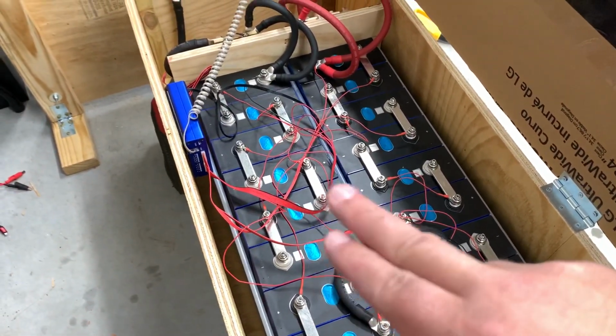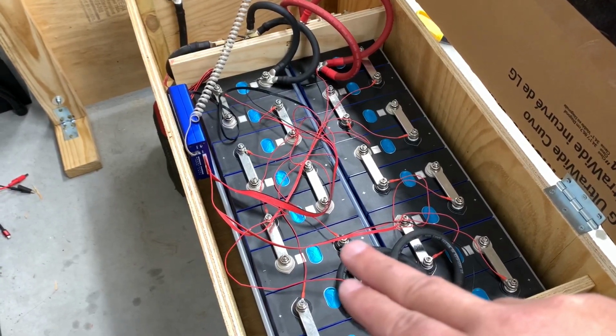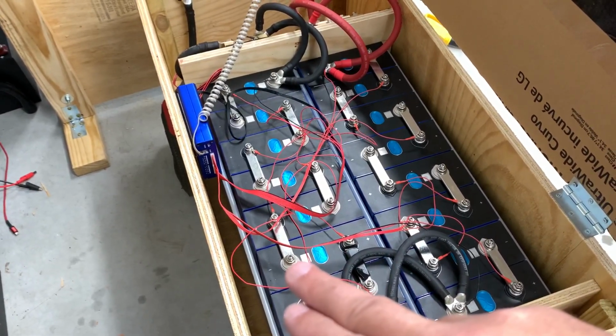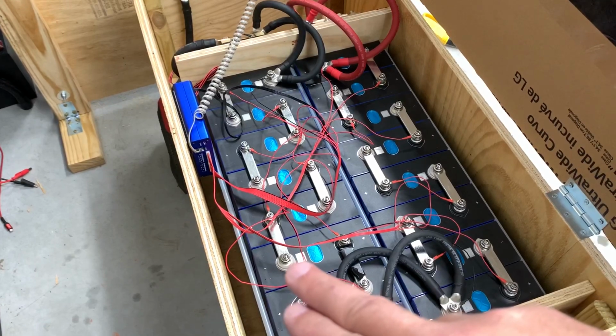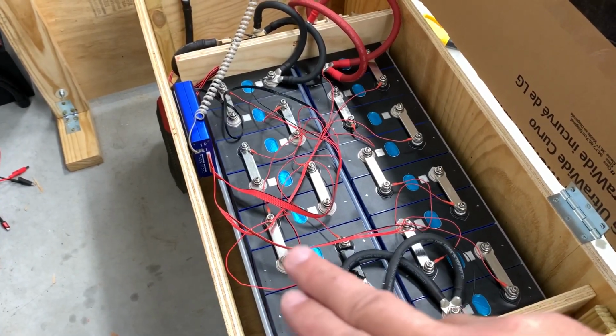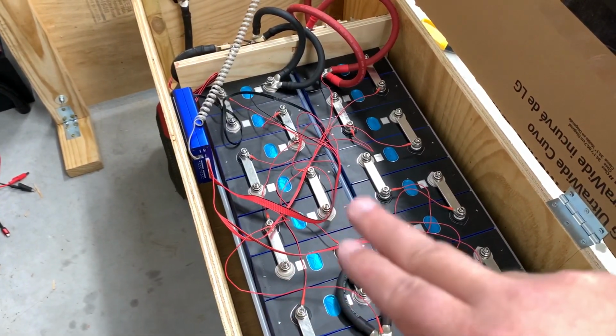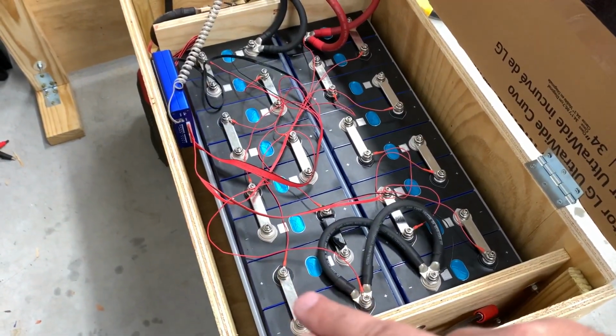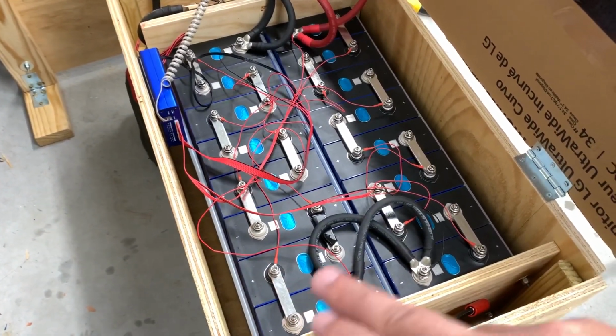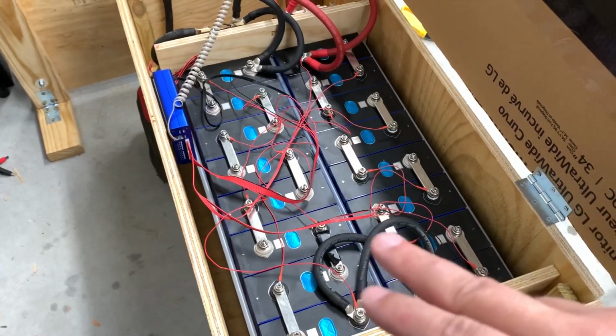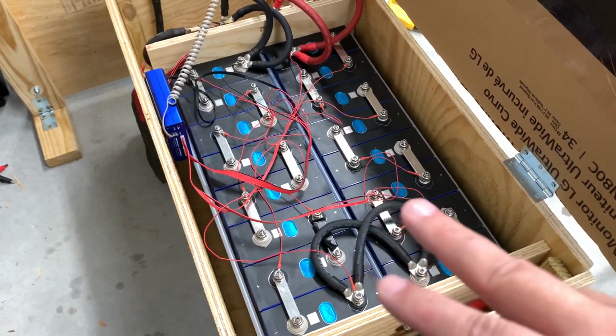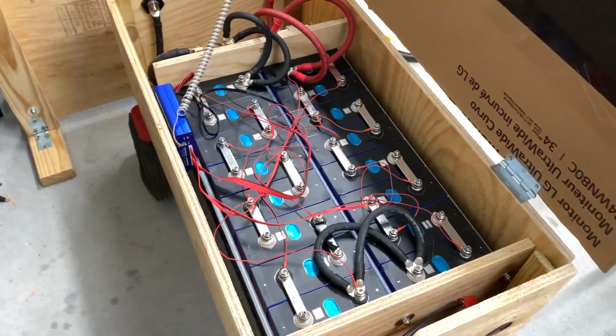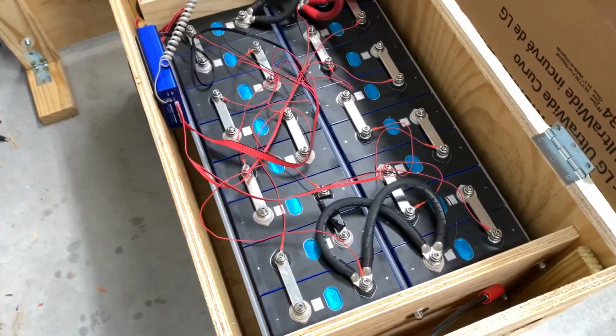I had some Loctite, since these studs are secured using Loctite. Some Loctite had wicked up and got underneath the bus bars, creating resistance between the bus bars and the cell. These were starting to heat up, and I was getting all kinds of crazy readings in the BMS, and the BMS actually ended up cutting out. So I had to disassemble and reassemble everything.